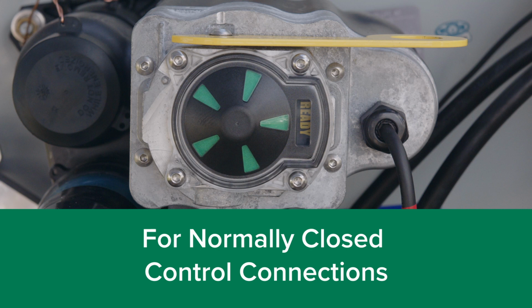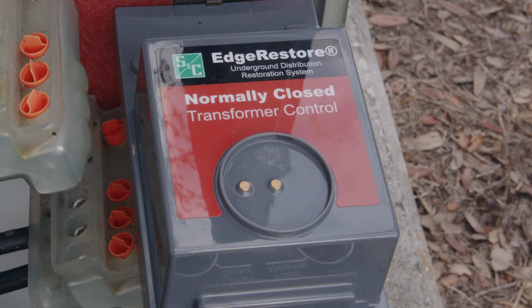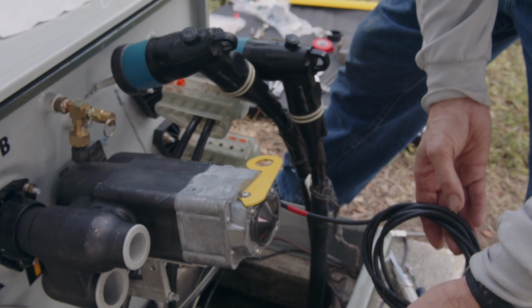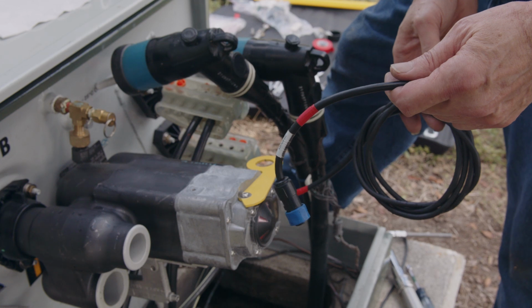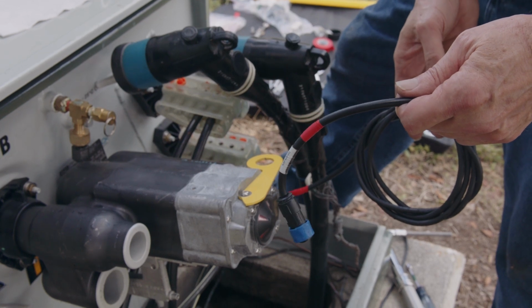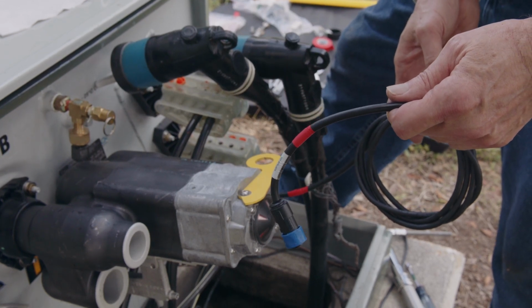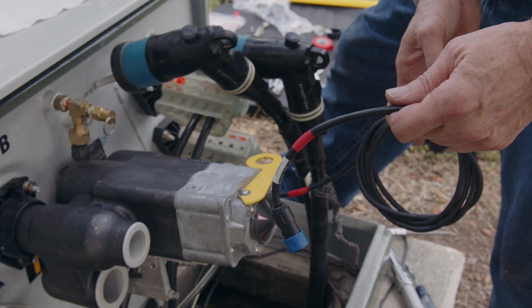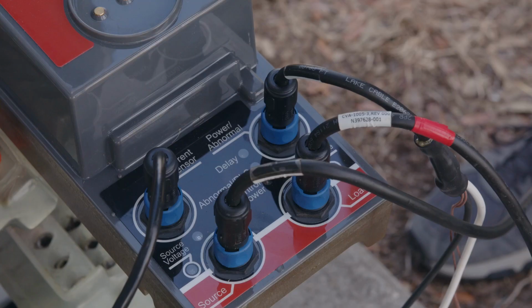Follow these steps for normally closed controls. Normally closed controls are identified by a red label. Note, there is a red band on the H1B control cable to help differentiate the H1A and H1B cables from each other when making connections to the control. Ensure that the H1A and H1B cable connections are correctly connected to the control based on the direction of current flow, load or source, through the transformer.